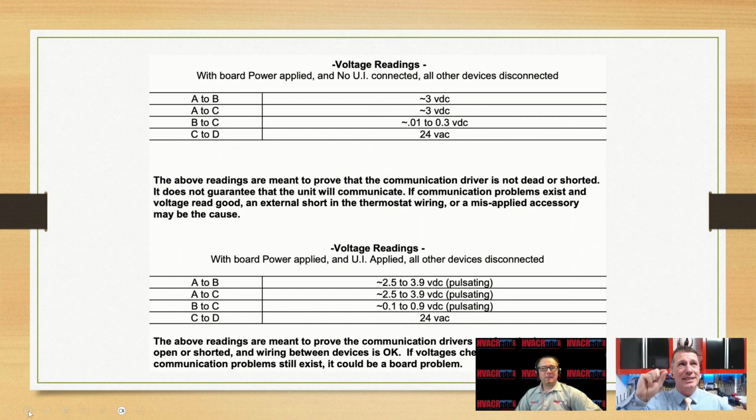And if we go from C to D, well, that looks awfully hot to me, and awfully familiar. That looks like an R to me, and they're all in reference to C. A, B, and D are all in reference to C. So C must be common.